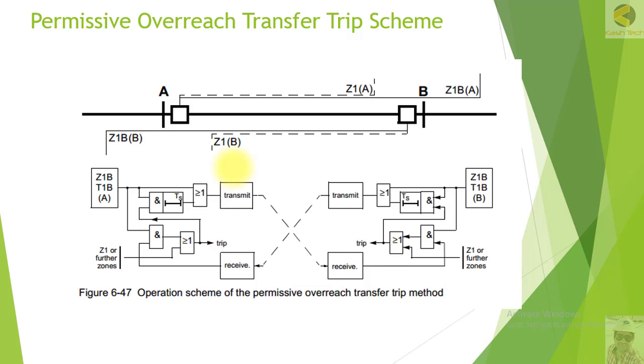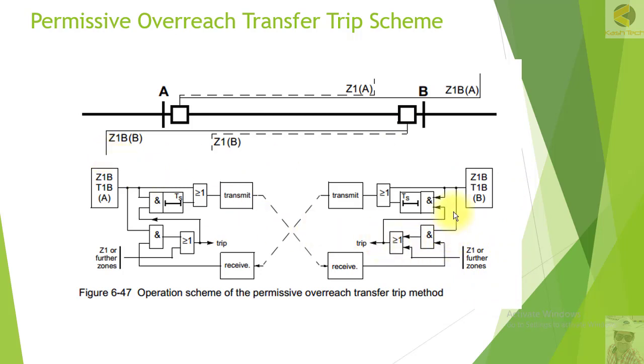In the permissive overreach scheme, the relay sends the permissive command to the remote end when it picks up in Z1B — this is the same as in PUTT. This scheme is normally used on short lines. For example, if the short line impedance is 0.5 ohm, 80% of the line would be approximately 0.4 ohm, which is very small and difficult to set. In that case, permissive overreach transfer trip is a good option, enabling faster tripping.